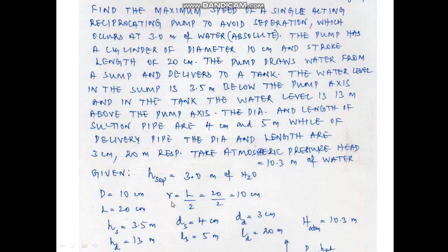The cylinder diameter is given, and the stroke, D and L. The water level in the sump is 3.5 meters below the pump axis, that is the suction head. And the delivery tank is 13 meters above the pump axis, that is the delivery head. Suction pipe length and diameter are given, delivery pipe length and diameter are given, and atmospheric pressure head is given. This atmospheric pressure head in terms of water is 10.3 meters. You need to remember this, they won't give it in the question.